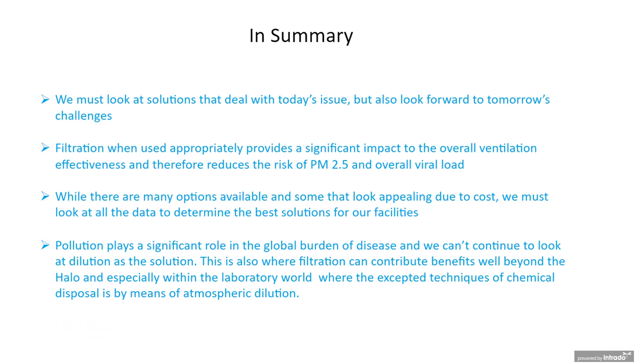So it's really a multi-pronged approach: ventilation, filtration, increase of air changes, proper disinfection and sanitization, and if necessary, UV if you feel it appropriate. So again, a very multi-pronged approach needs to take place. Very good. Now, does that answer also apply to the senior adult facility? It does, absolutely. It applies to all facilities. If it's senior adult, long-term care, hospitals, school settings, it really applies to all.